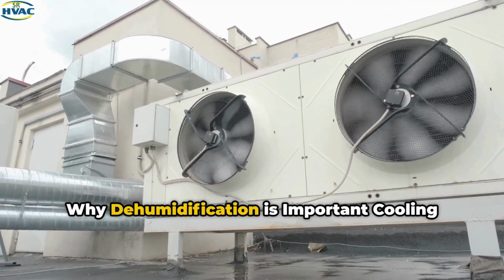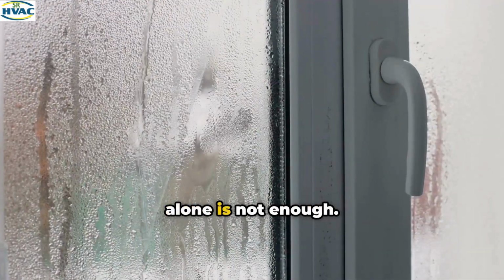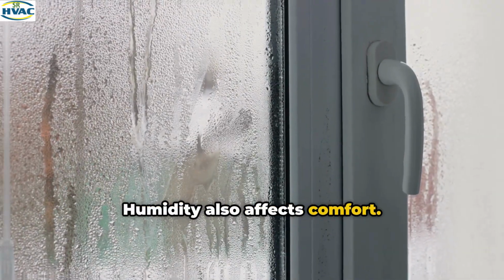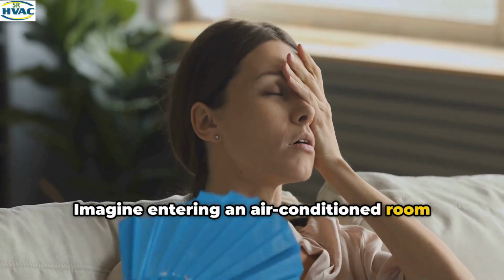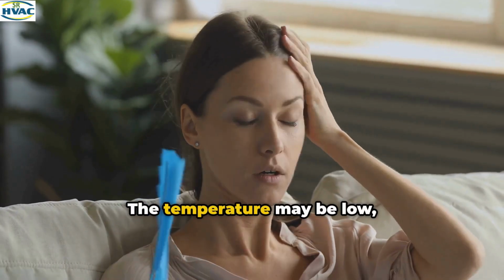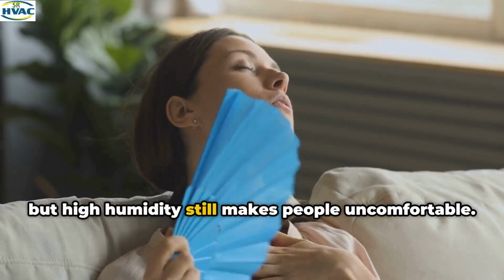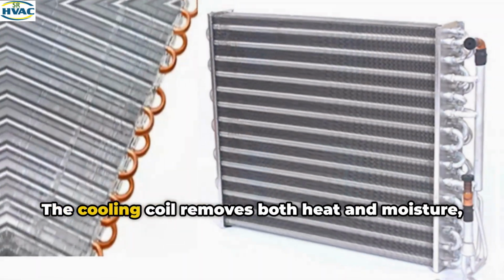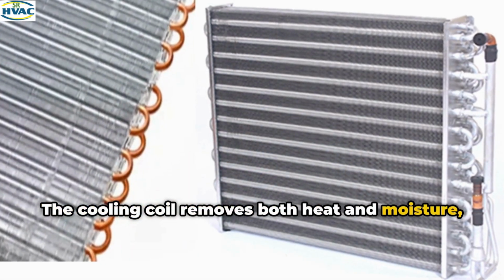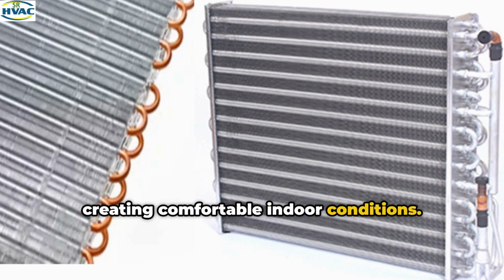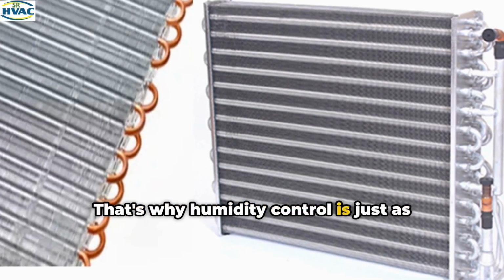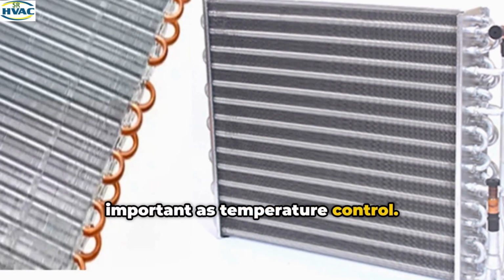Why dehumidification is important? Cooling alone is not enough. Humidity also affects comfort. Imagine entering an air-conditioned room that feels sticky. The temperature may be low, but high humidity still makes people uncomfortable. The cooling coil removes both heat and moisture, creating comfortable indoor conditions. That's why humidity control is just as important as temperature control.